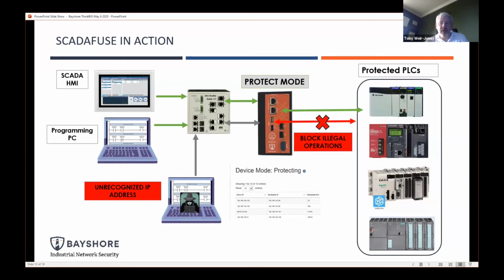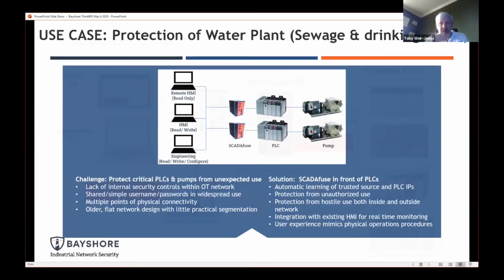But what happens if you have a learned IP and it normally has read-only access, but now it tries to do a write or a programming change? Same thing. Doesn't matter if you piggyback off the IP, the violation occurs because we see it at the function code level because of the deep content inspection that the SCADA fuse is performing. So here's another use case. This is a pretty standard water plant.